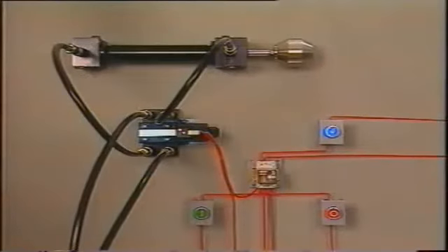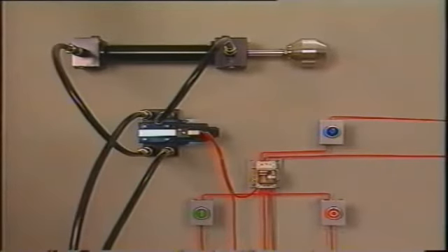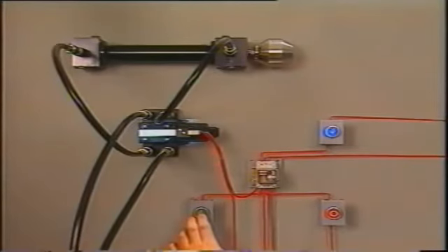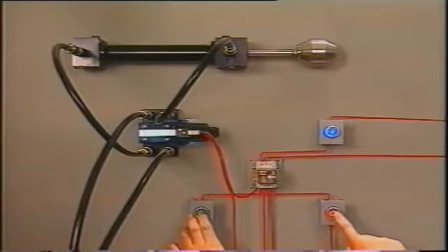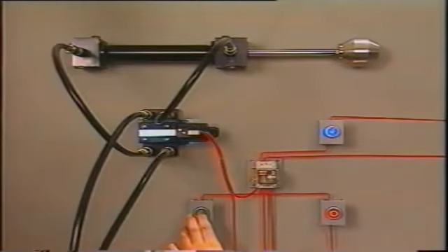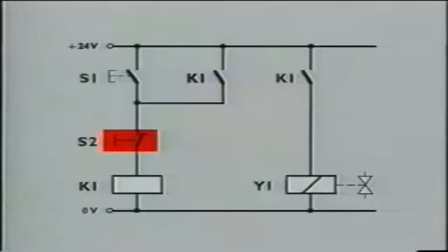An example. In this circuit, the ON signal remains effective even if the OFF signal is given at the same time. This means that the machine step is automatically completed once started. This is another latch circuit. But in this case, the OFF push button S2 is not connected in parallel as before, but in series to push button S1.